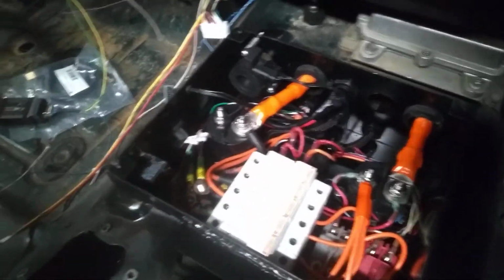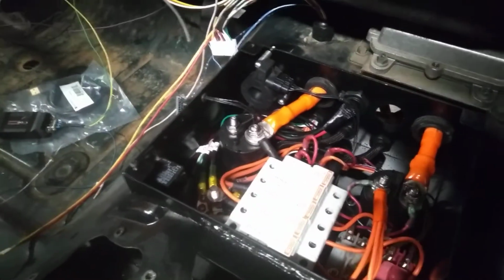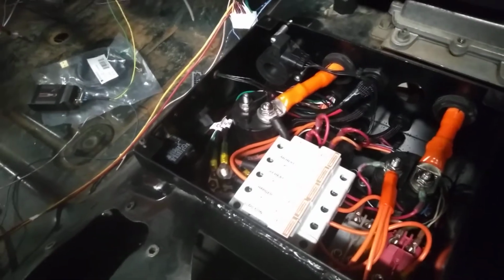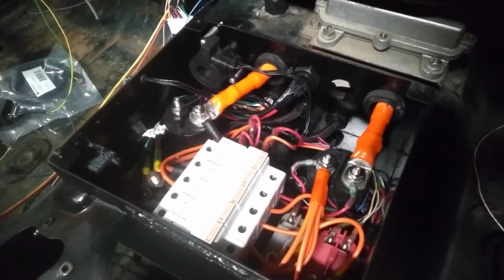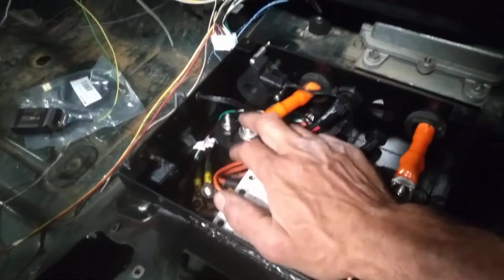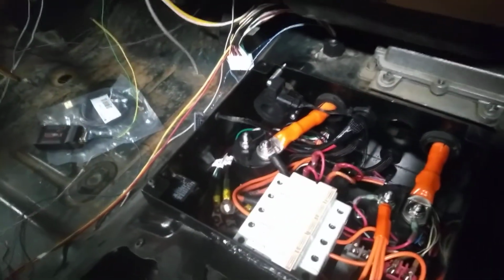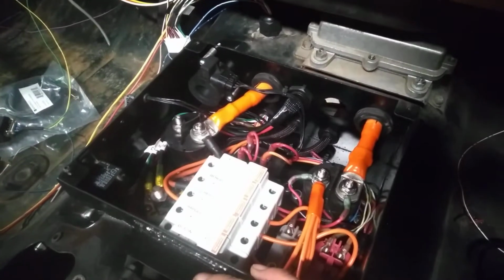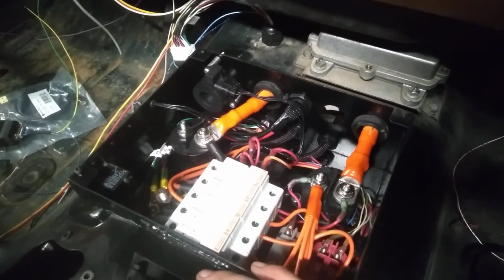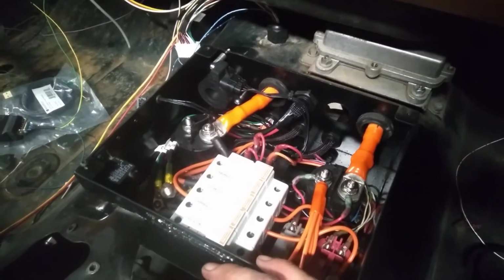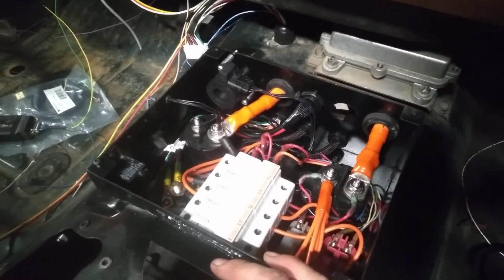I've got a little relay over here that's used so the BMS can control... which one does it control? Oh, it controls the negative contactor, because that negative contactor is attached to the discharge enable of the BMS.